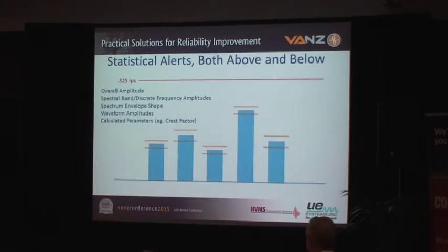And I'm a firm believer that once you have history on a machine, and this applies on a location by location, sensor by sensor basis, measurement location by measurement location basis, and specific measurement type to specific measurement type basis. Consistency. When you've got the consistency that you need, and you know you've got it, focus on the statistics, because really this is all change analysis.